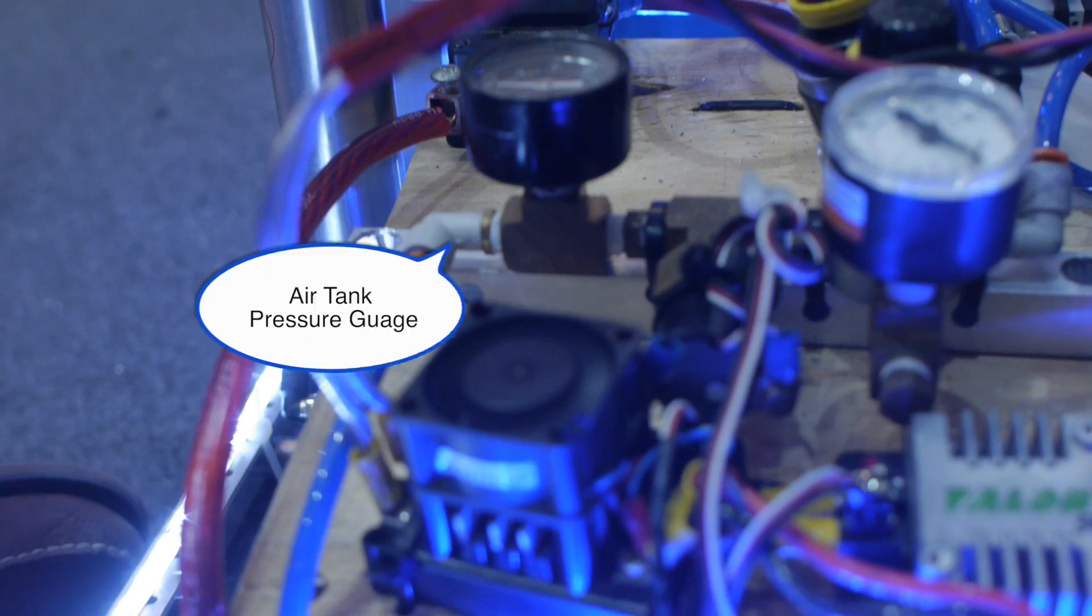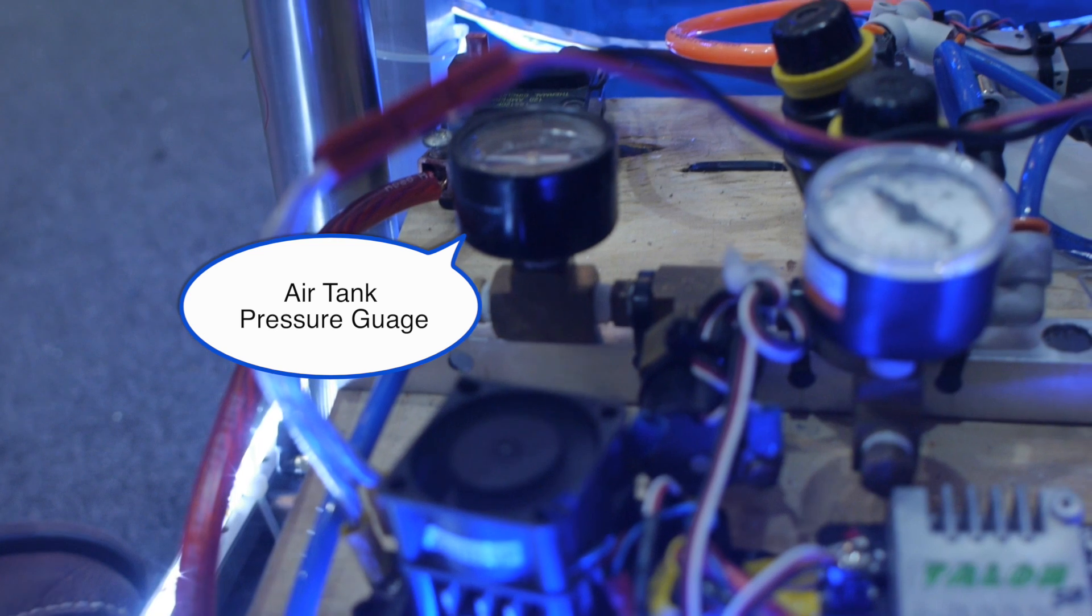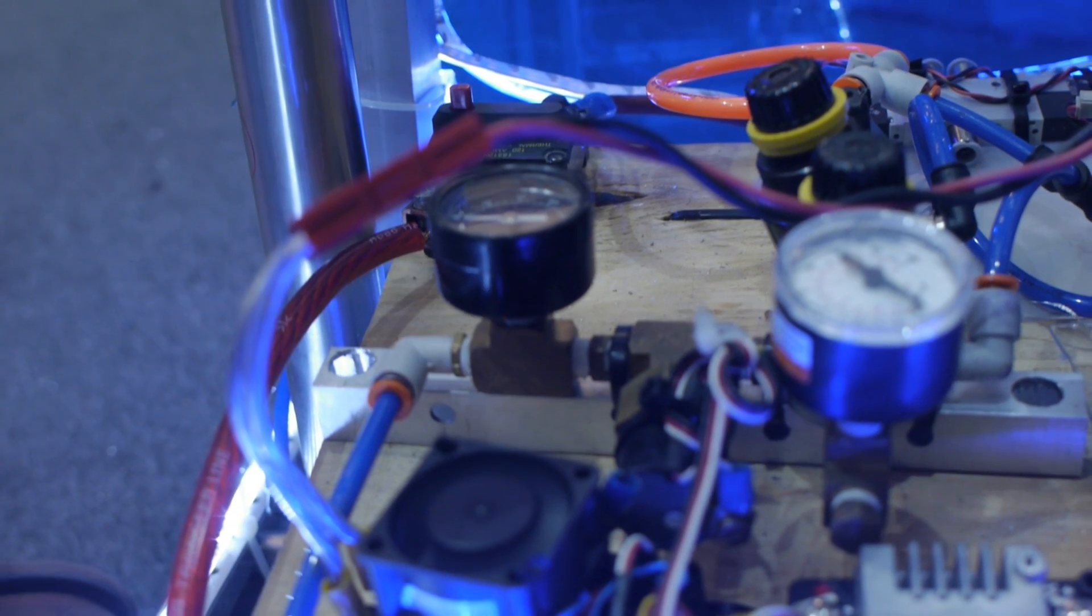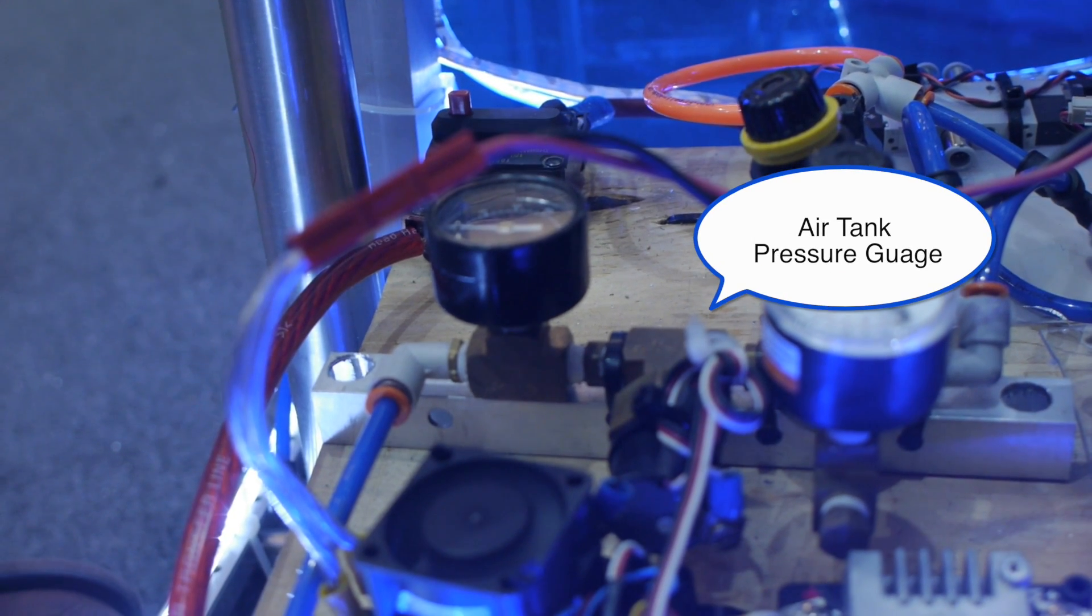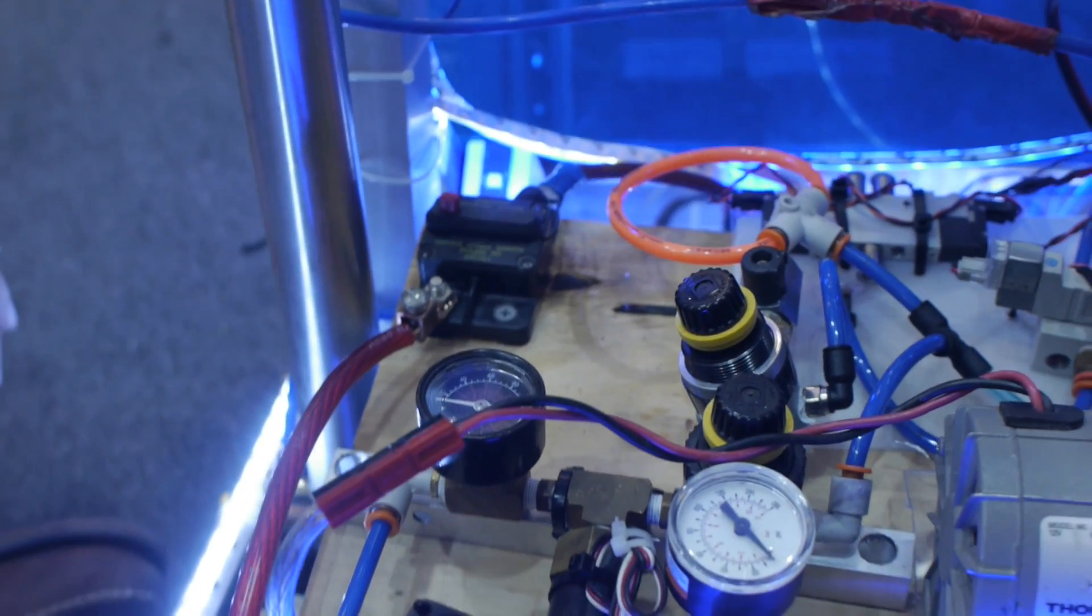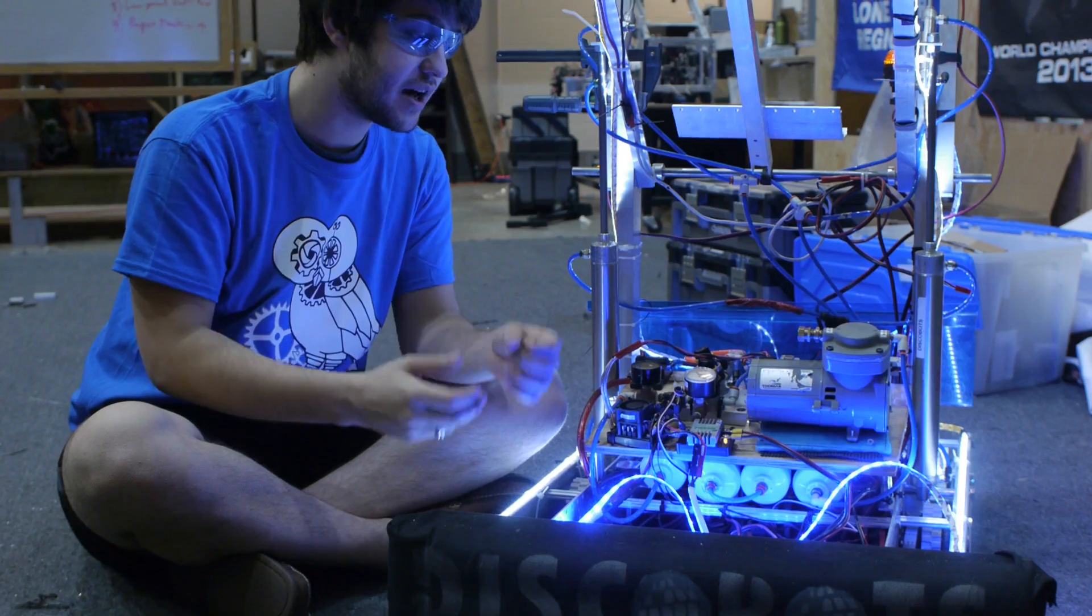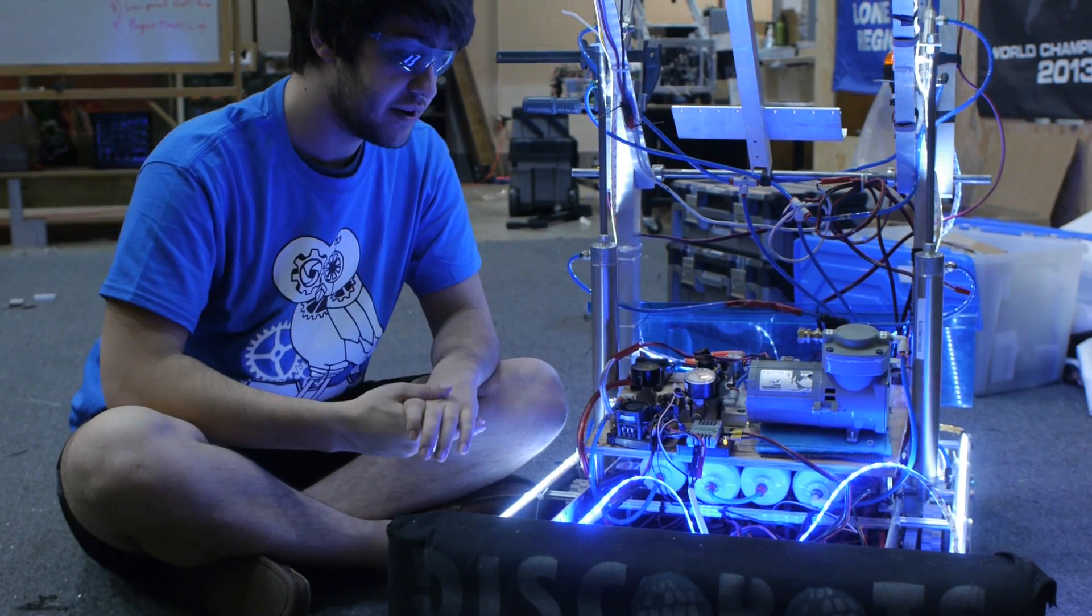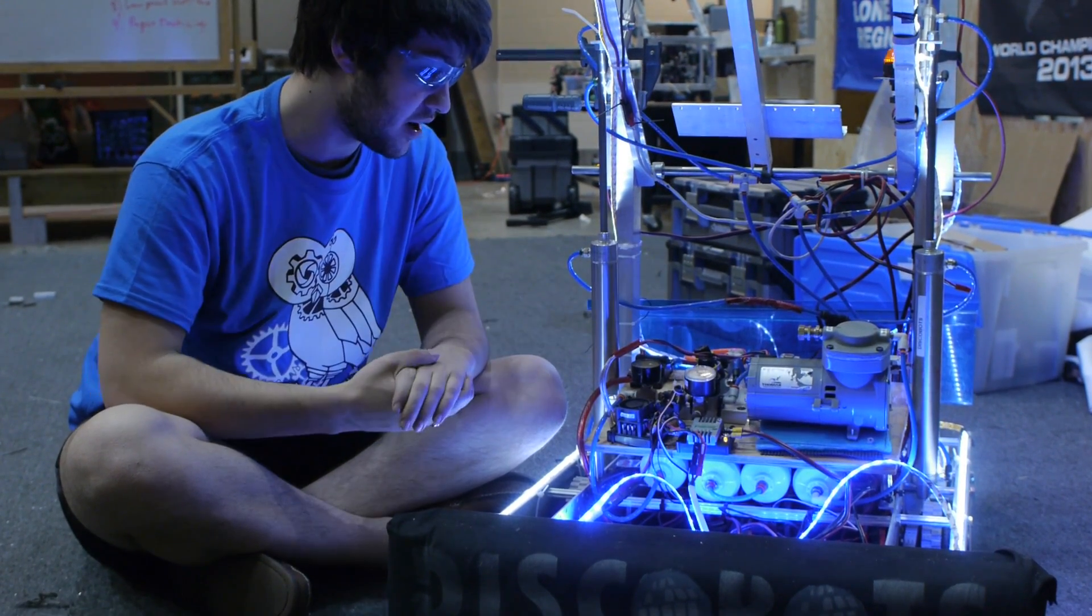From the tanks, the air flows into this gauge where you can read the air pressure of the tanks. From that, it flows into the sensor which regulates the compressor. If the air in the tanks is under 120 psi, it turns the compressor on. If it is at 120 psi, it turns the compressor off.